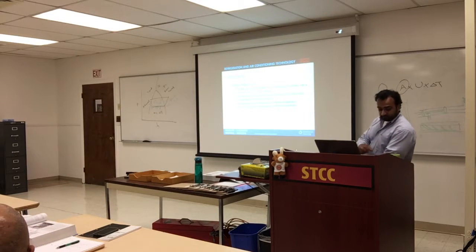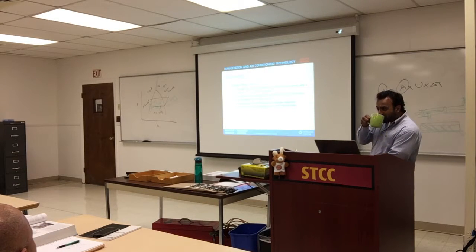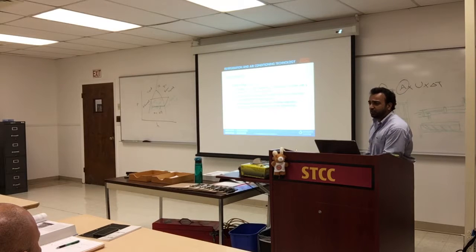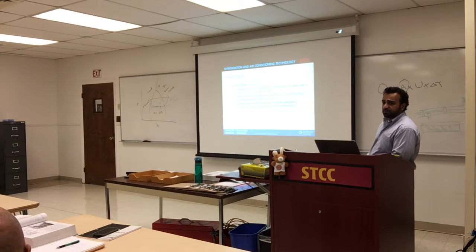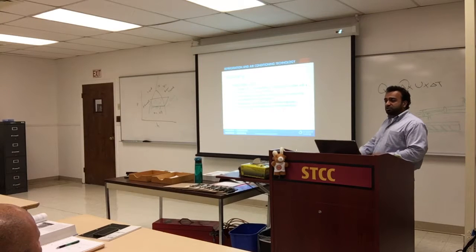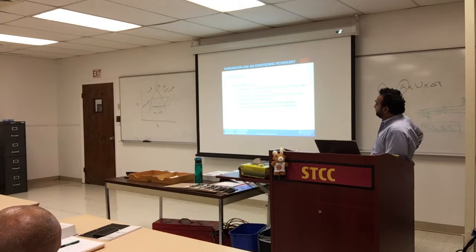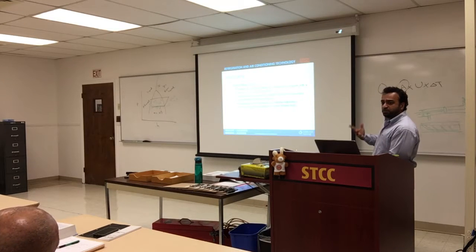So if your condenser is plugged up with pollen, would that mess with it? Definitely. We'll see that. We'll have it running and we'll cover up the condenser. It won't reject the heat and you'll see the pressure drop. So it becomes very interesting. It's kind of like magic when you look at it.